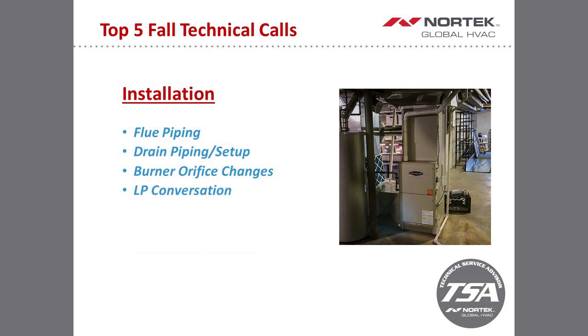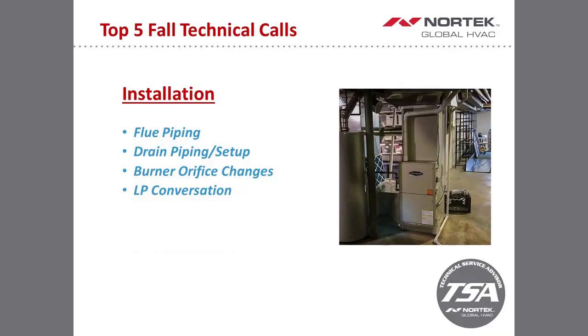On the LP conversion, again, you will be switching to newer orifices on the burner manifold, and along with that the gas valve will have to be converted. Now, depending on if you are on the residential side, you'll be changing out springs on the gas valve. If you're on the manufactured housing side, if it's on the single stage stuff, you'll be just flipping the cap over on the gas valve and it'll be red in color and stamped LP on that little cap.